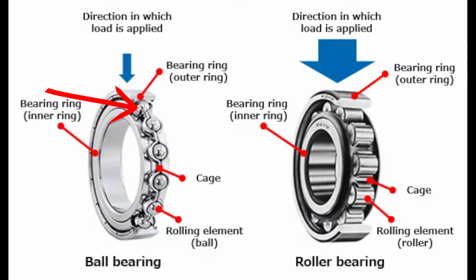So your new bearings will almost always come, if you order just a standard bearing, they will come with shields. Now you can get them with no shields, but let's stick with a simple example of a pump motor. If you're installing these into a pump motor, then you're going to want to get them with shields. Don't get the non-shielded. And in that particular case, you'll want one shield to be removed, and it'll be the outer side. So if this was our rotor and stator here in the middle between these two bearings, just follow along with me if you can, then this outer side is where our grease housing is going to typically be.